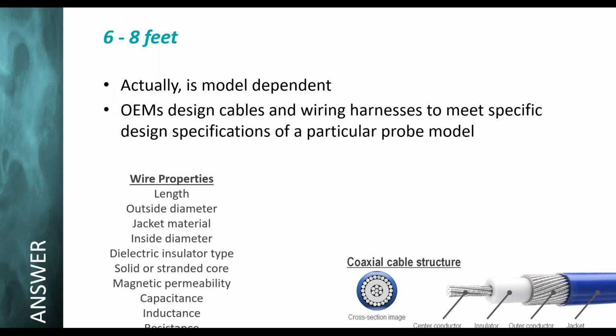These are all the different wire properties. One of the things we do in Tulsa is manufacture over 80 different transducer cables. On the market there's a one-size-fits-all cable you can buy raw, cut to length, and fit to any transducer. We don't believe in that, because each has different properties: capacitance, inductance, resistance, solid or stranded conductors, different insulators. Again, it's about OEM form, fit, function. If the OEM did it this way, a repair provider should be doing it this way.